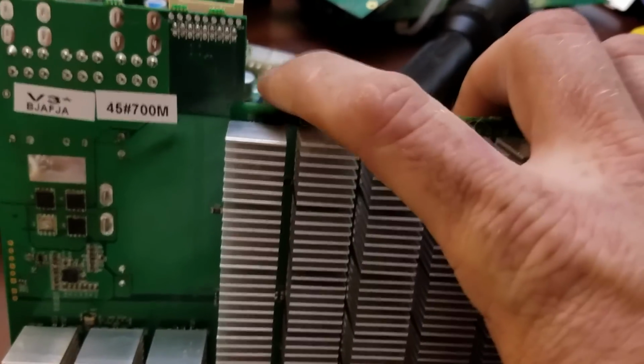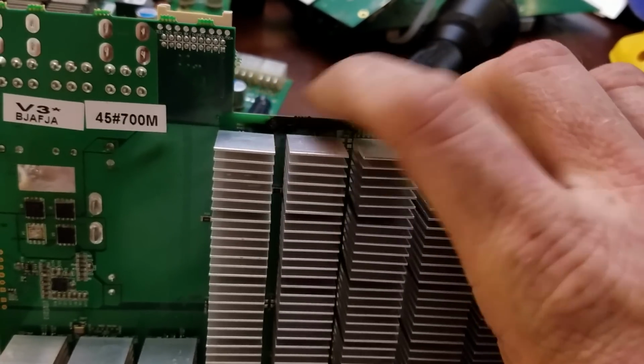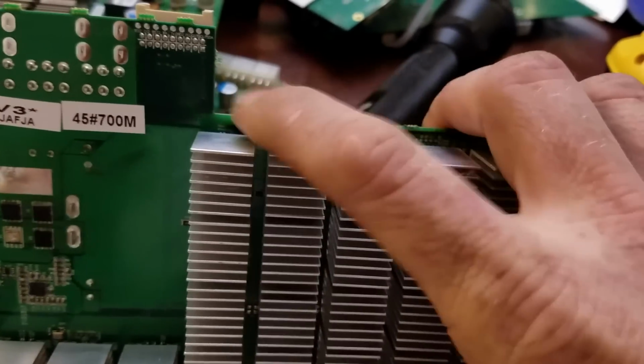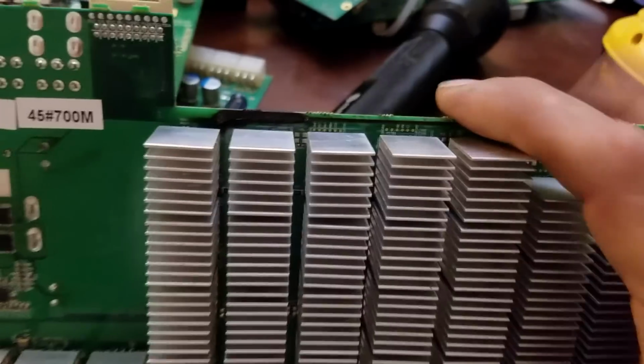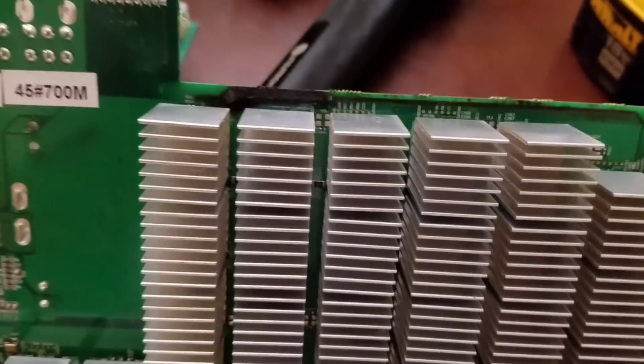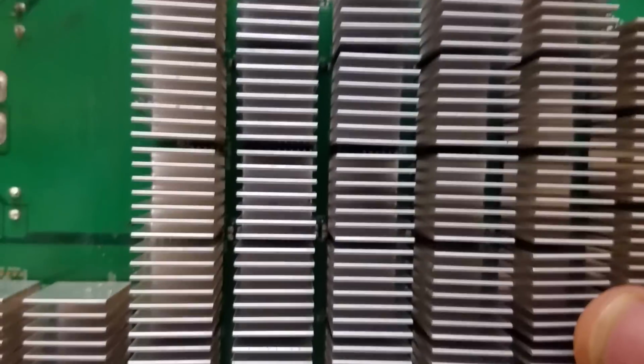It's usually right here at the top because the aluminum housing is actually colder than the air passing across it, because it's got air blowing across it. And then if the moisture in that air begins to condense, and bang, board's dead. As you can see, this one here, the line all the way across right there shorted completely. So this board is dead. This one is basically no repairing it.